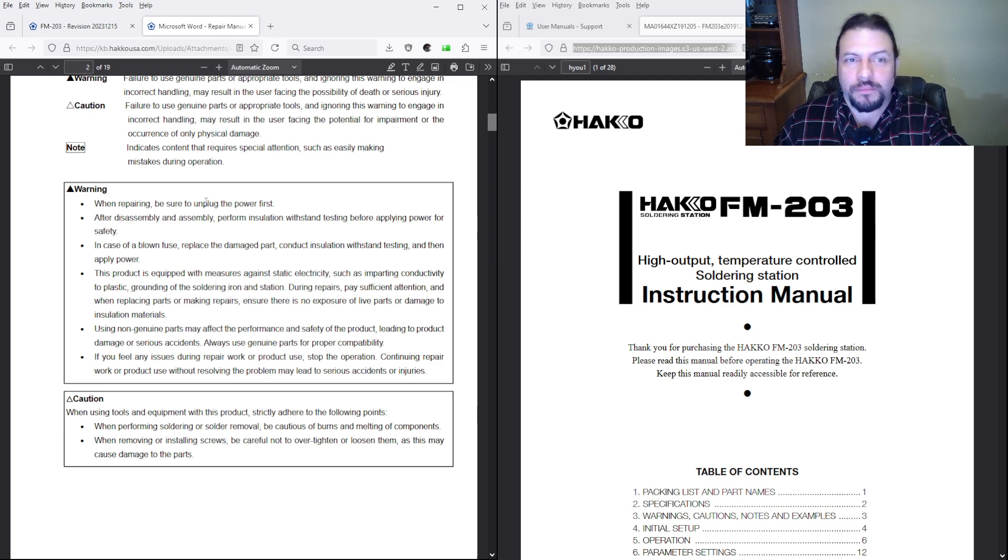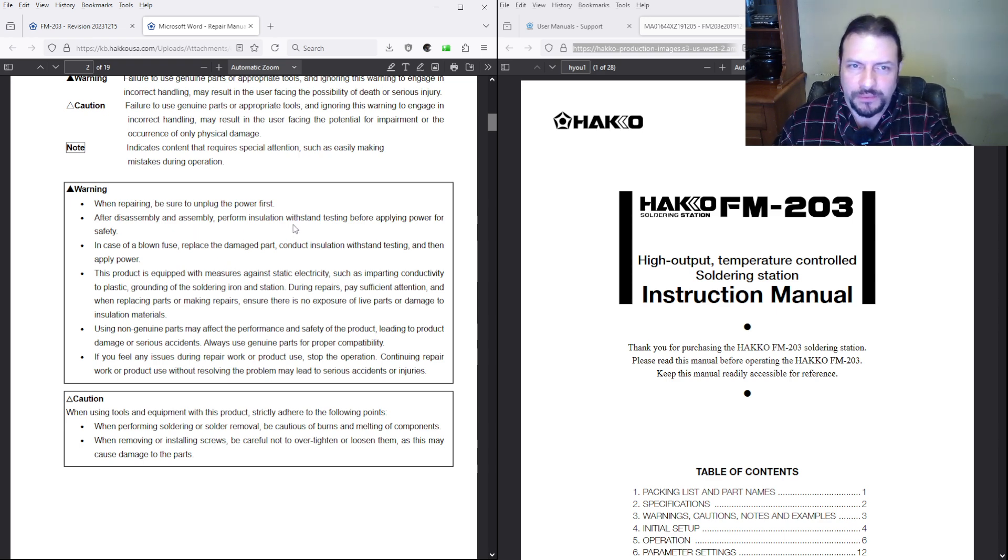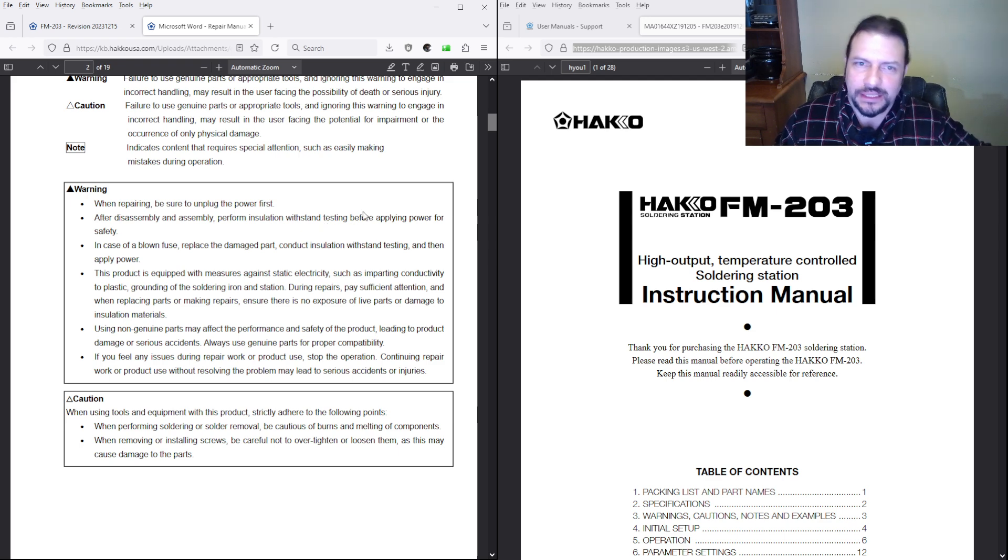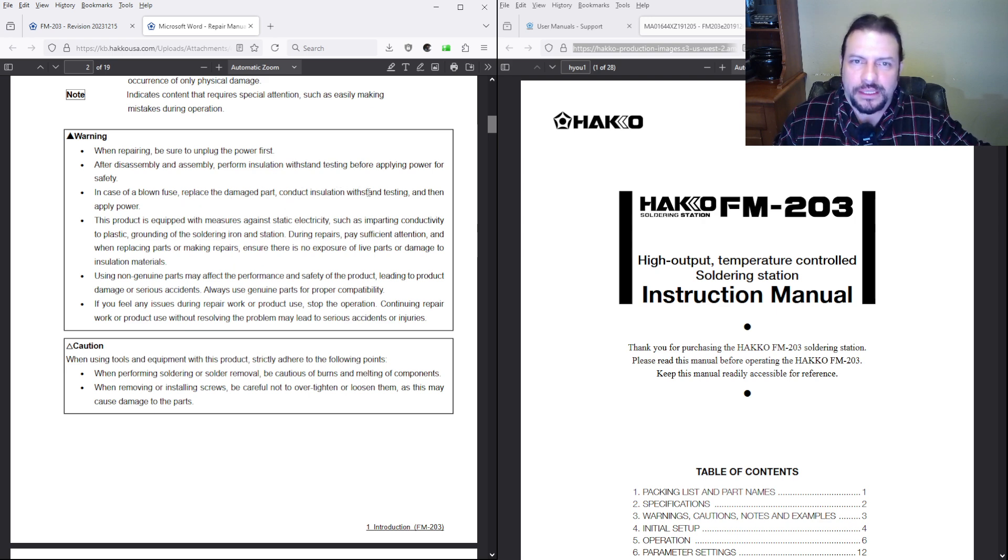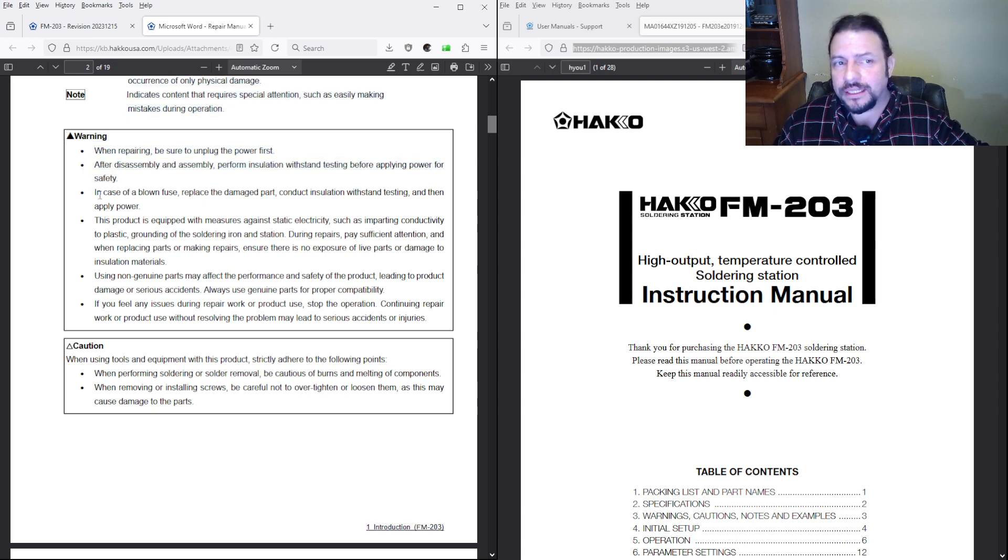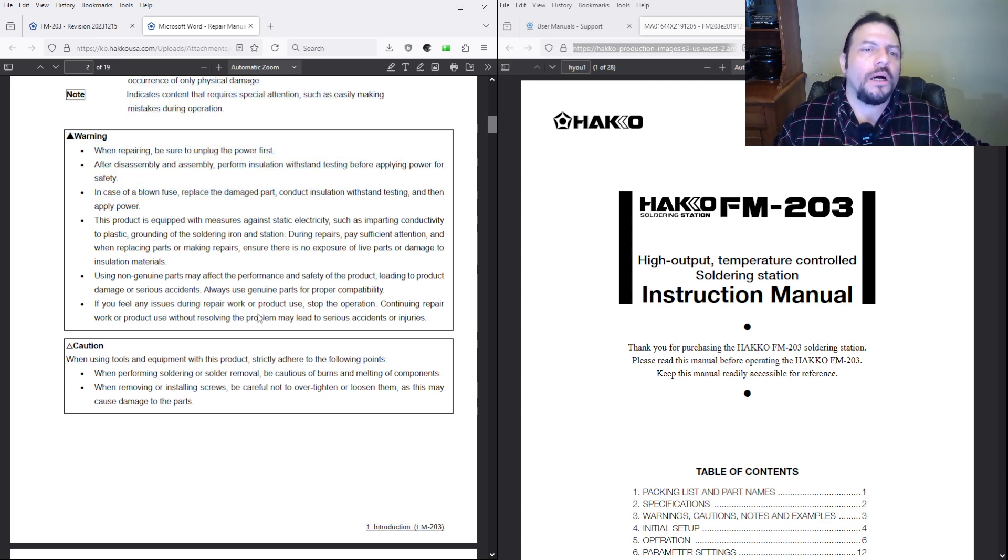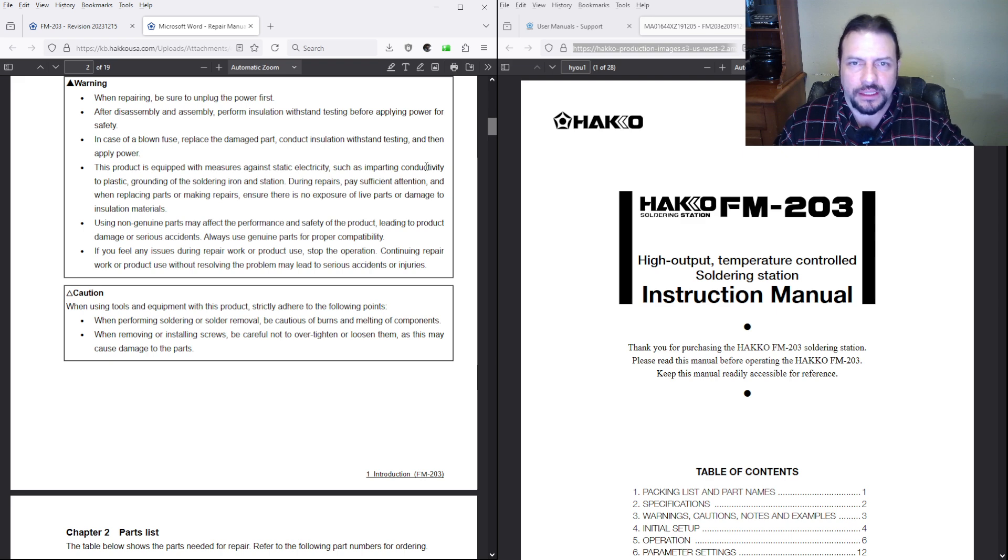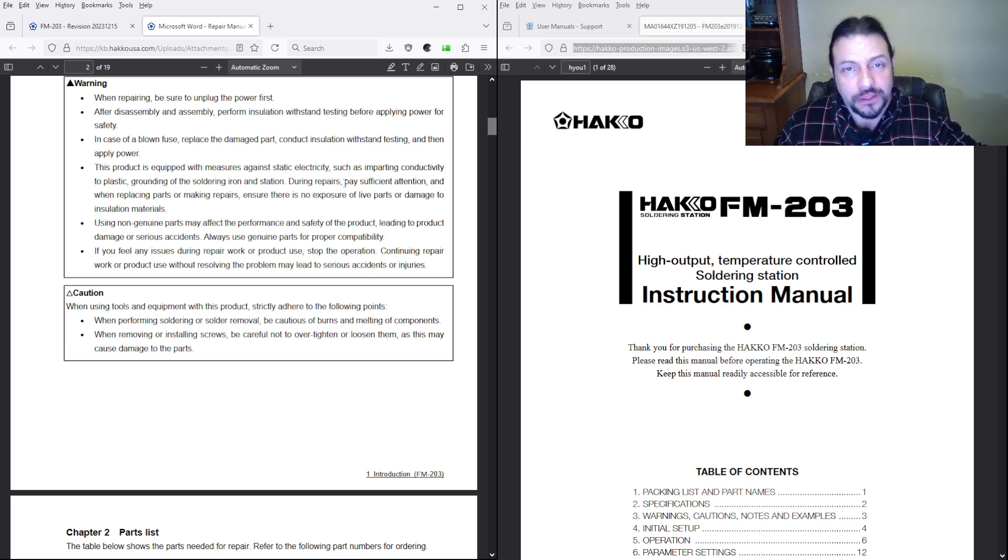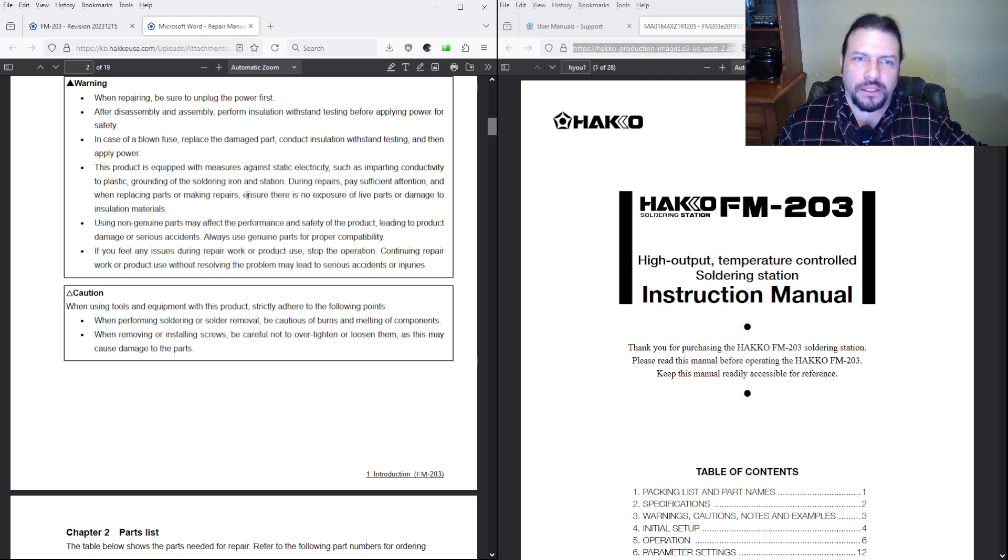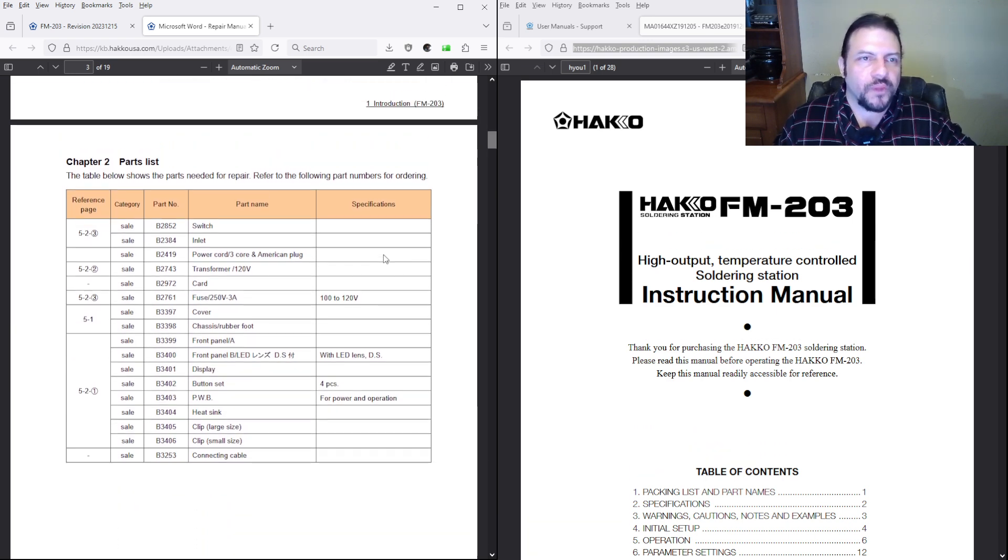When repairing, be sure to unplug the power first. Okay, well sometimes you have to have it powered up to diagnose. After disassembling, perform the insulation withstand testing before applying power for safety. In case of a blown fuse, replace the damaged part, conduct insulation withstand testing, and then apply power. They're really focusing on this insulation withstand testing. Hakko, are you trying to tell us something? Maybe you got a design flaw. This product is equipped with measures against static electricity. Pay sufficient attention, and when replacing parts and making repairs, ensure there's no exposure to live parts damage. Okay, standard bullshit.